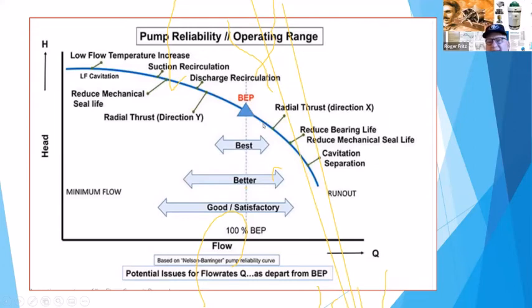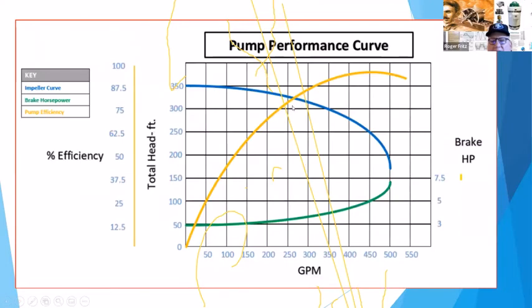So you'll get such things as water hammer. You'll get a lot of effect of surging motors, especially if you're at the higher point of the head pressure, dependent on where that pump impeller was cut and turned to at that given speed to give you its optimal performance. Everything likes to be balanced.